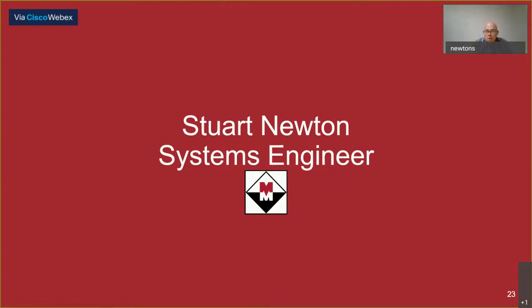I'm going to take a little bit of time and continue on and talk a little bit about the automation and control of the starting devices that Gino's already chatted about. First of all, I'd like to take our minds back and remember how the original starting devices were in fact activated. Obviously, way back when, before networks and all, we would operate these things on a standalone basis, probably in a manual mode, typically push buttons, select switches and those things. And then with the advent of PLCs, we got some level of automation using discrete I/O to start the devices with some kind of a wiring solution. And then from then, with the introduction of simple networks like remote I/O, DH+, Modbus, there was a network option between the drives or the devices and the PLC.